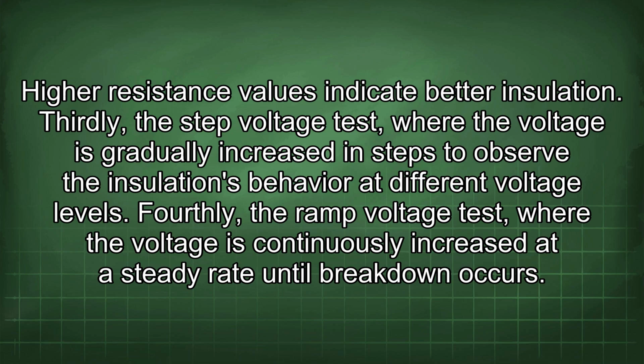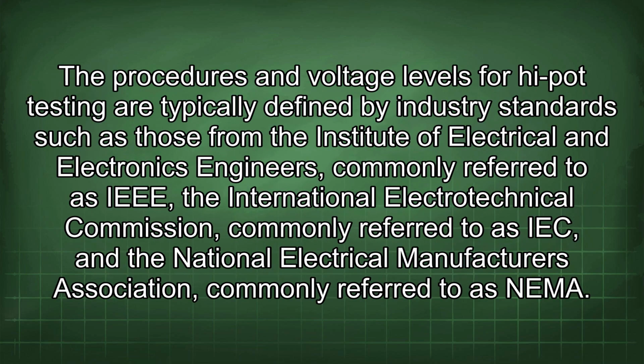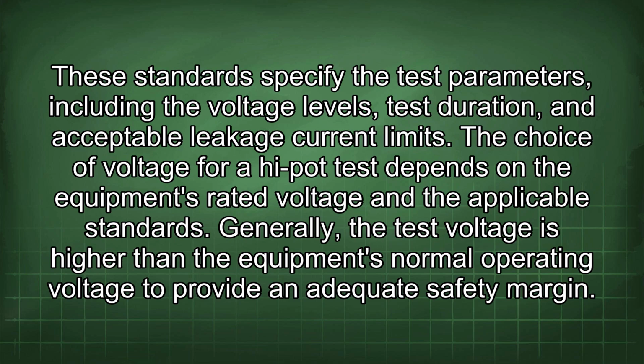Fourthly, the ramp voltage test, where the voltage is continuously increased at a steady rate until breakdown occurs. The procedures and voltage levels for high-pot testing are typically defined by industry standards such as those from the Institute of Electrical and Electronics Engineers, commonly referred to as IEEE, the International Electrotechnical Commission, commonly referred to as IEC, and the National Electrical Manufacturers Association, commonly referred to as NEMA. These standards specify the test parameters, including the voltage levels, test duration, and acceptable leakage current limits.